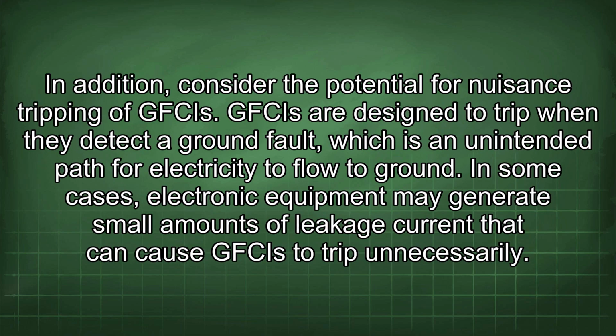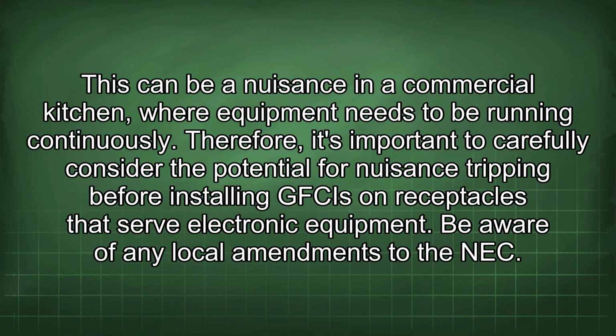In addition, consider the potential for nuisance tripping of GFCIs. GFCIs are designed to trip when they detect a ground fault, which is an unintended path for electricity to flow to ground. In some cases, electronic equipment may generate small amounts of leakage current that can cause GFCIs to trip unnecessarily. This can be a nuisance in a commercial kitchen, where equipment needs to be running continuously. Therefore, it's important to carefully consider the potential for nuisance tripping before installing GFCIs on receptacles that serve electronic equipment.